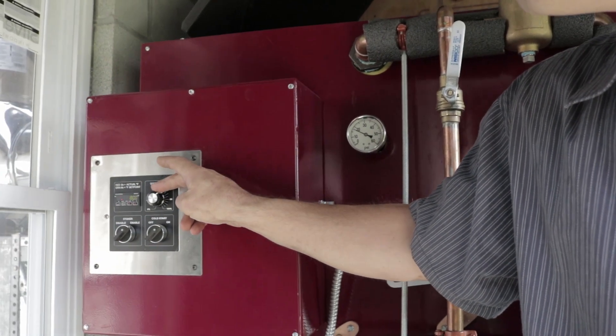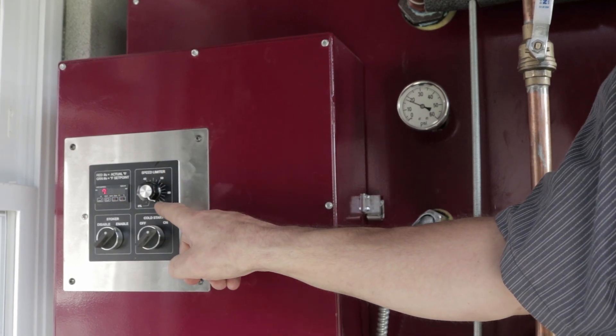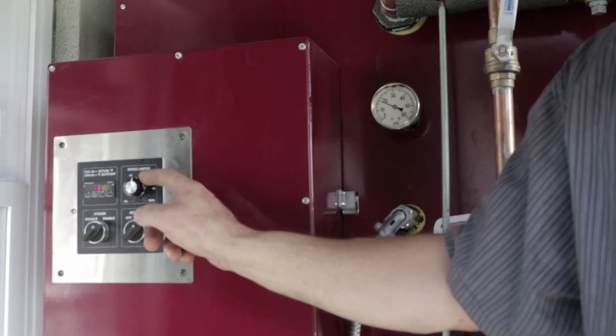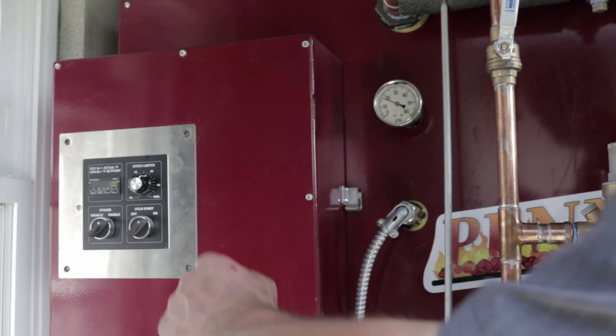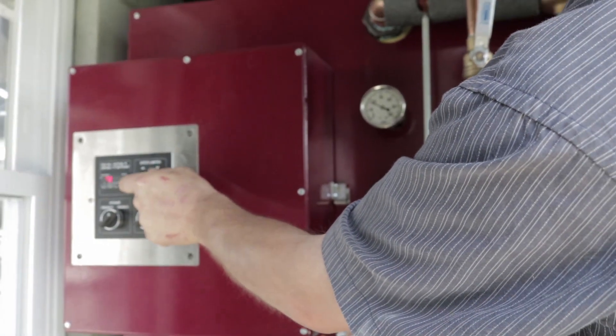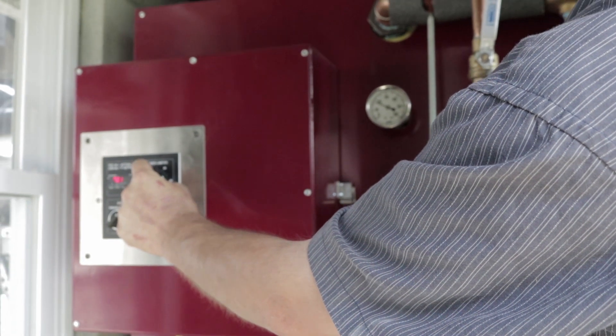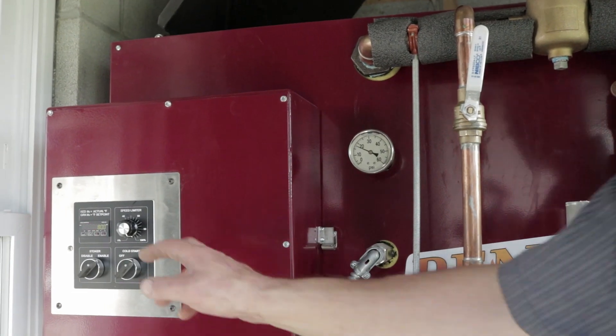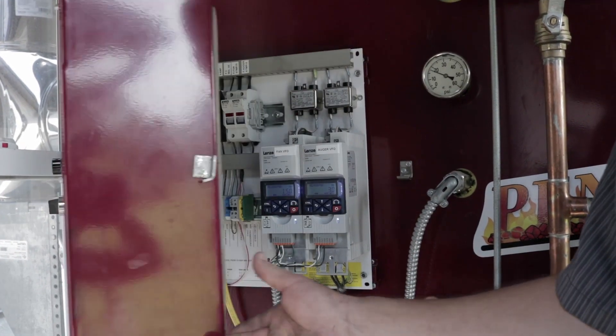This knob and dial gives you manual control over all that operation. If you run it wide open at 100%, it runs completely off the automatic control. This allows a manual override to further limit the firing rate beyond what the controller calls for — that's why it's called a speed limiter. Essentially, this knob does manually what the controller does automatically: 0 is idle, 100 is full bore, and that range is the bandwidth.